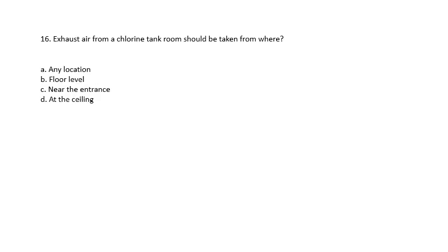Question 16: Exhaust air from a chlorine tank room should be taken from where? Any location, floor level, near the entrance, or at the ceiling. The answer is at the floor level, because chlorine is heavier than air.